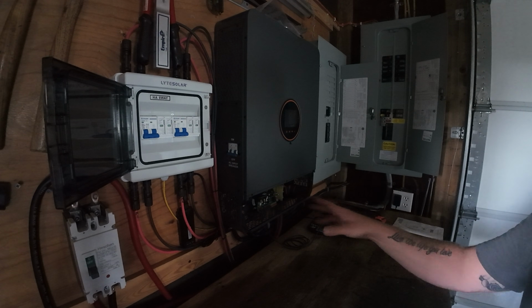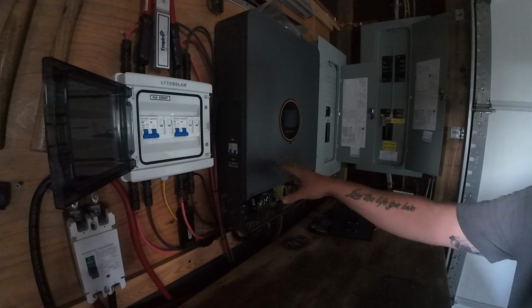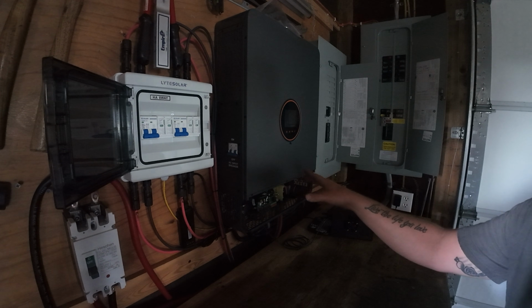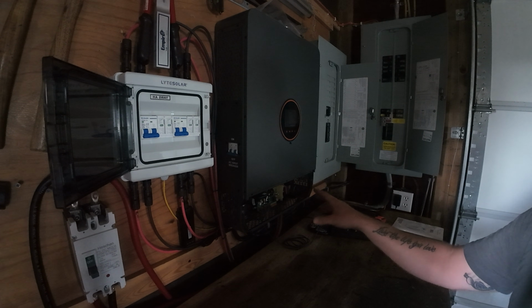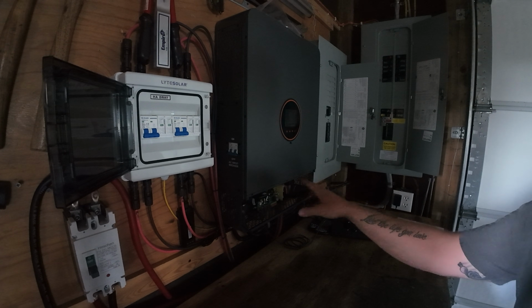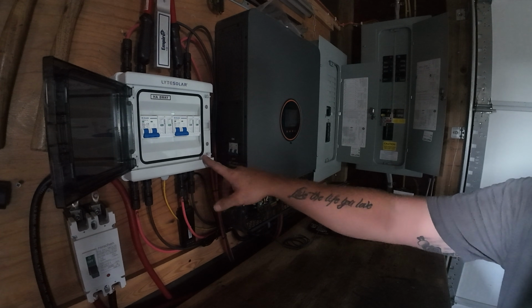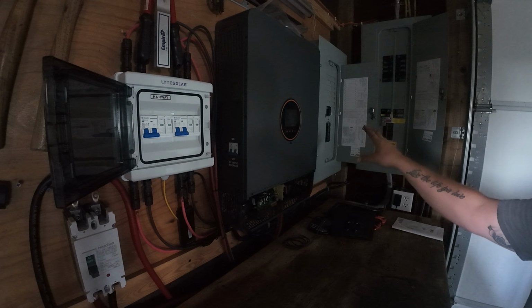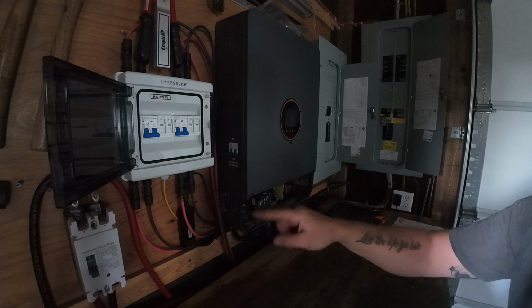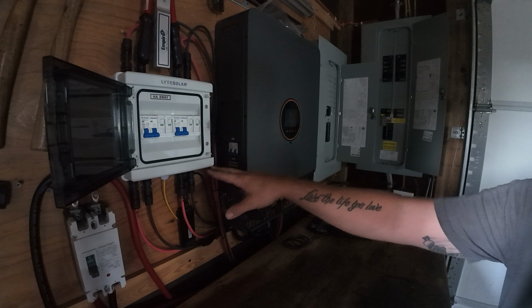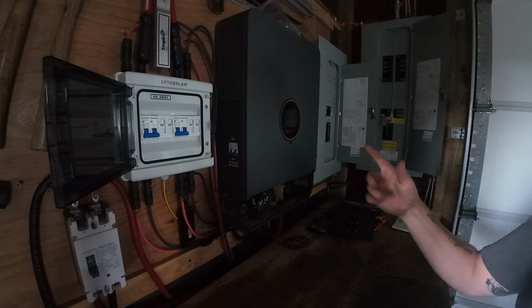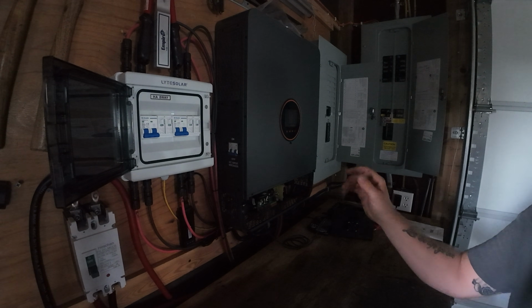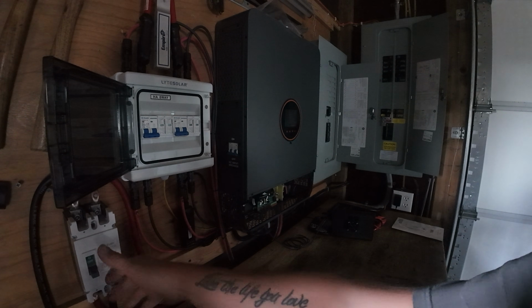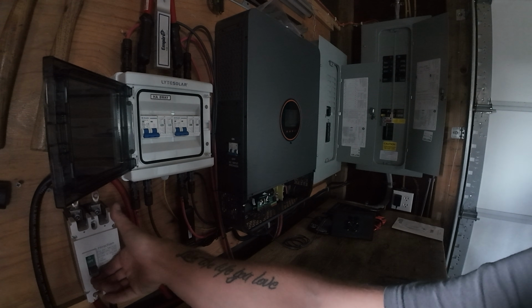Alright, so before we start the sequence, this system can also be run without a battery—it can be run with or without one. As you've seen before, I was running it without a battery, so the sequence was different then. Without batteries, you'd just turn the PV system on first, then go on with the rest of the sequence. But once you have batteries, you actually have to turn on the battery breaker first, then the PV breakers, then the rest of it. So it's a little different depending on what you've got installed. But if you've got it installed like I do, the first step will be to turn on the battery breaker. So let's do that.